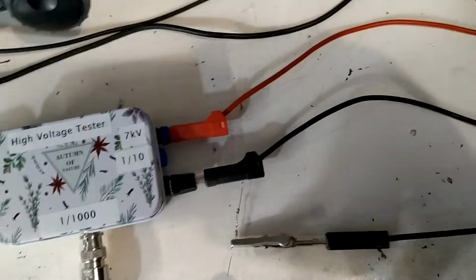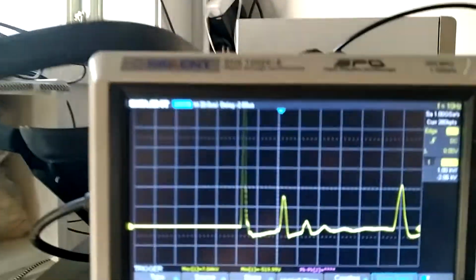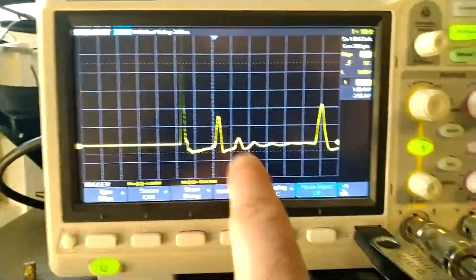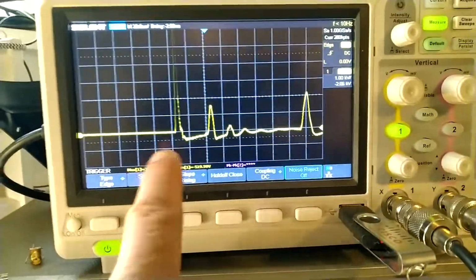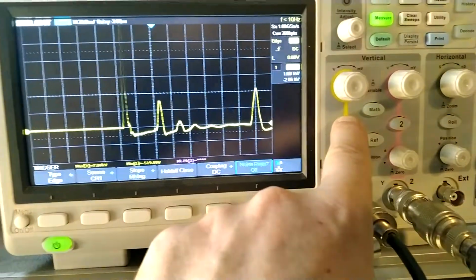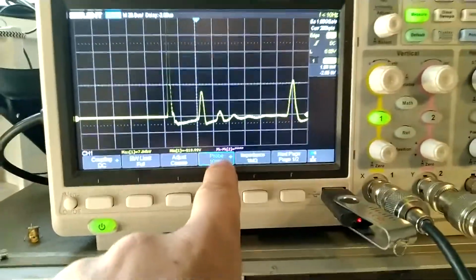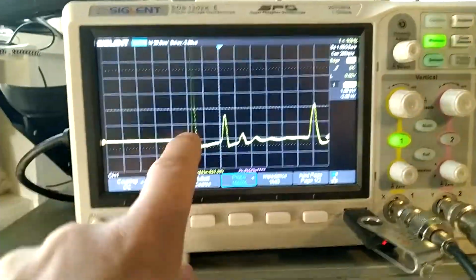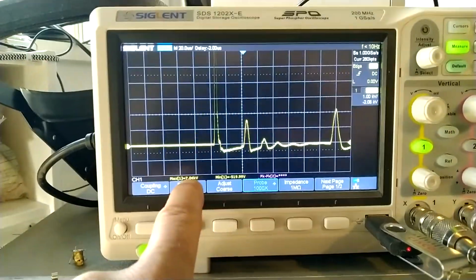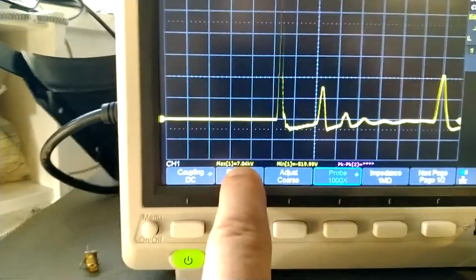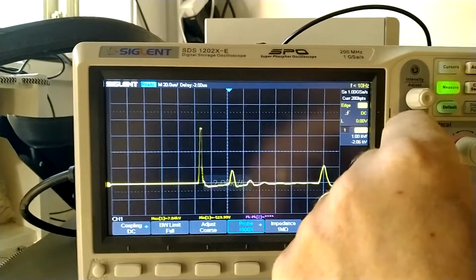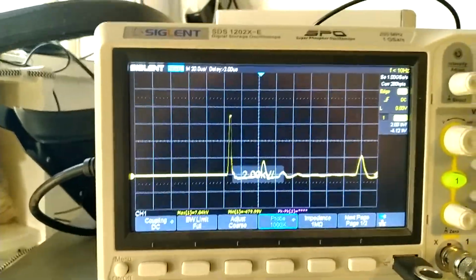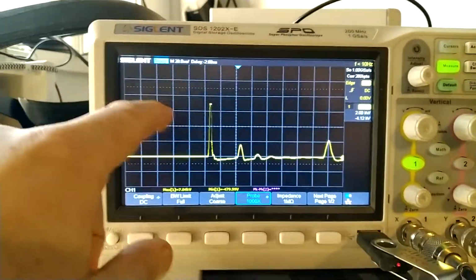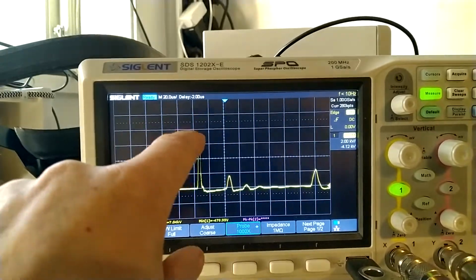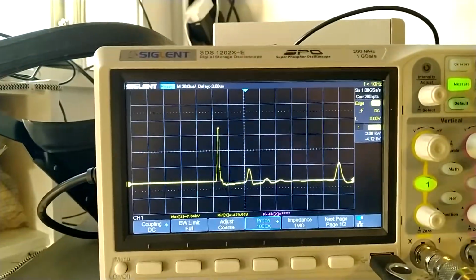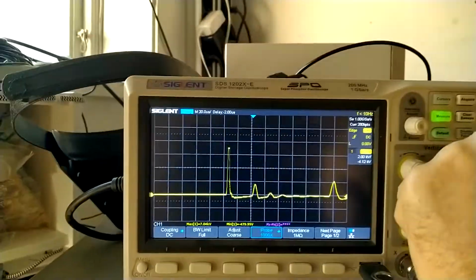Okay, there was a spark, I saw it. And here's the pulse on the oscilloscope. It's set so that it actually calculates correctly in kilovolts now because the probe is times 1000. So this here is measured at 7 kilovolt, as you can see there. So it's quite a sharp event. It's probably a bit more than 7 kilovolt because the oscilloscope clipped it there. But anyway, there you see the pulse.